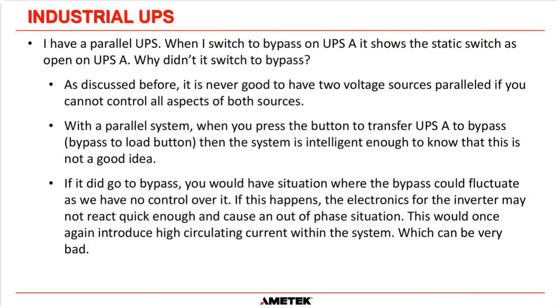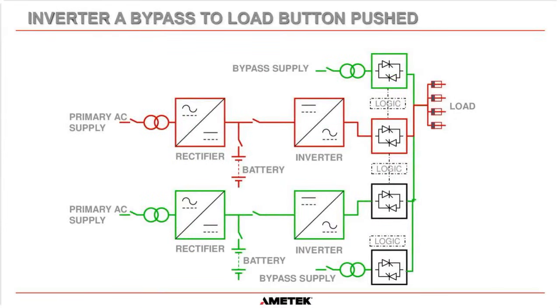So our parallel systems are intelligent enough to know that. So instead of turning UPS A static switch to bypass to load, we'll switch off the static switches on UPS A and allow UPS B to feed all of the load circuits. I think, do I have a drawing? Yeah. So you can see here that these static switches, this is UPS A, they're both off because somebody pressed bypass to load on that system. But UPS B carries on feeding the load circuits regardless. Okay.